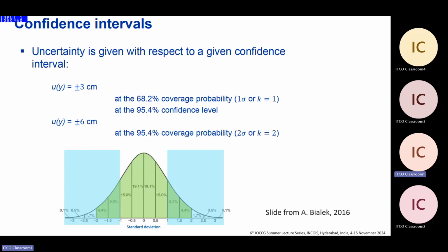And that's one of the last things from the radiometry, the metrology part: people in the metrology domain generally report their uncertainties either at what they call k equal 1 or k equal 2. That's just about the fact that you consider 1 or 2 standard deviations in your uncertainty distribution.